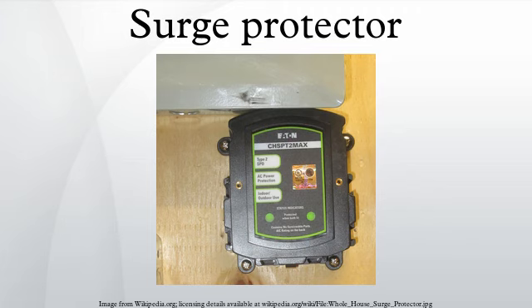Some manufacturers commonly design higher joule-rated surge protectors by connecting multiple MOVs in parallel. Since individual MOVs have slightly different nonlinear responses when exposed to the same overvoltage, any given MOV might be more sensitive than others. This can cause one MOV in a group to conduct more, leading to overuse and eventually premature failure of that component. If a single inline fuse is placed in series with the MOVs as a power-off safety feature, it will open and fail the surge protector even if remaining MOVs are intact.